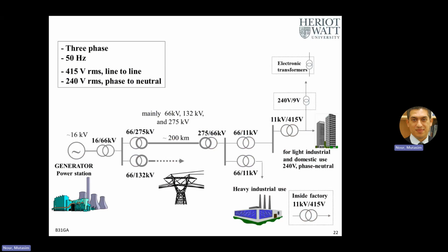So look, we have a step-up transformer, and we have two transmission lines. One 275 and 132. Why? What do you think? What is the difference between them? Normally, we step up the voltage to a higher level for long distances. So here, 200 kilometers. By the way, if it's 400 kilometers or more than 300 kilometers, we'll step this up to about 400 kilovolt, because for longer distances, you have to step it up in order to reduce the losses. Here, the distance is shorter, right? And so on.